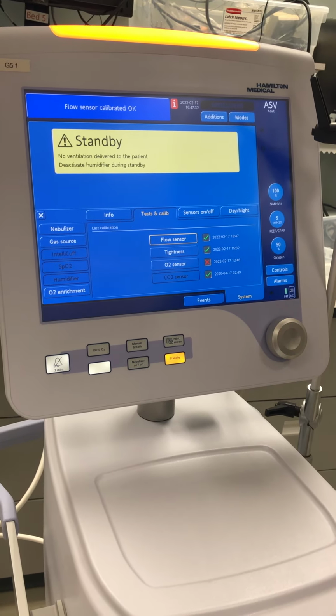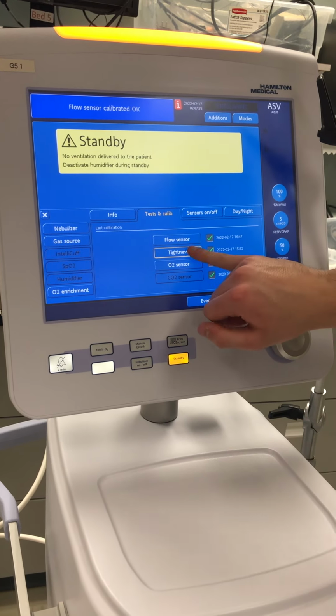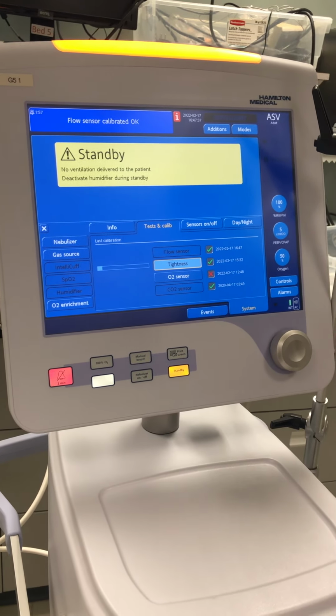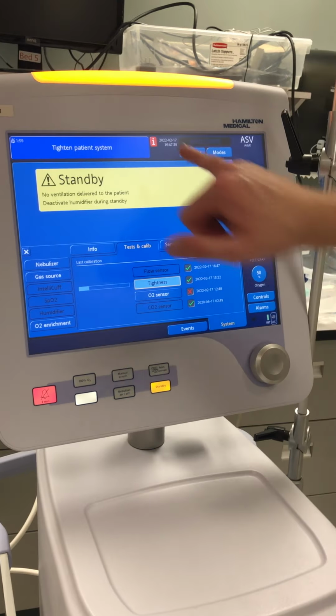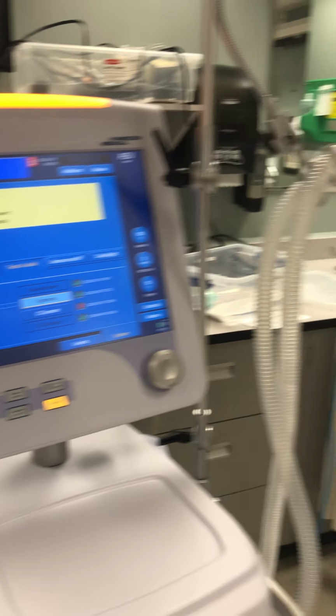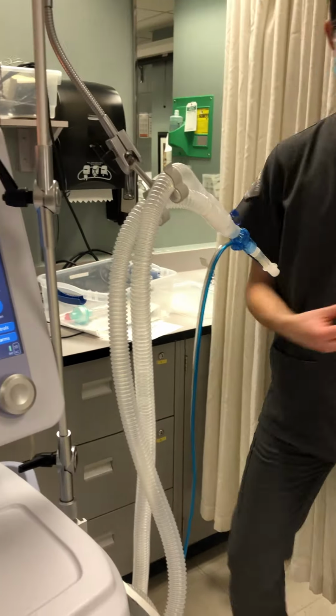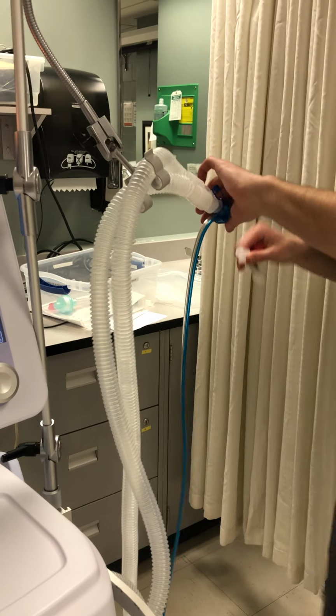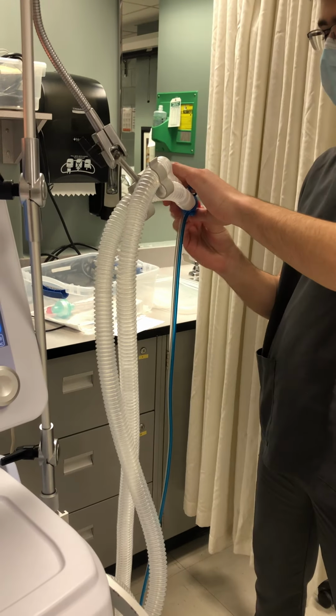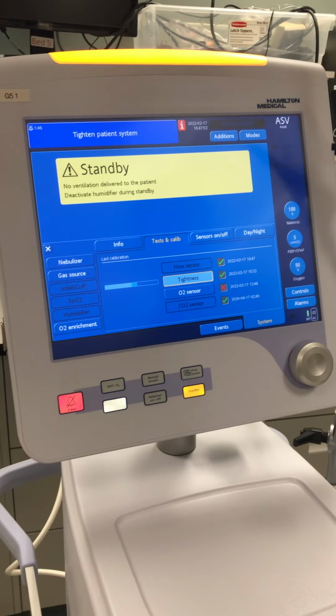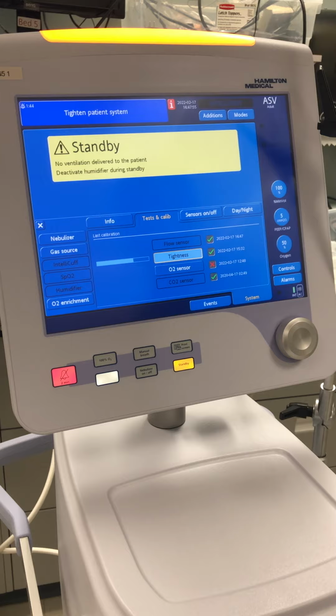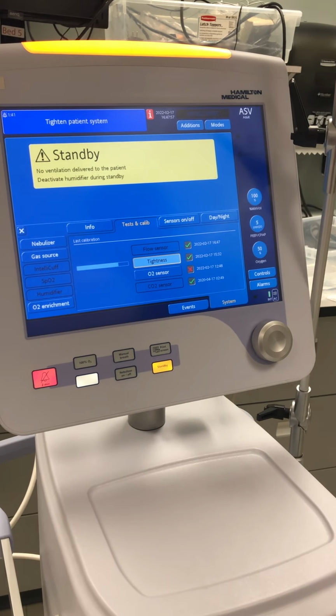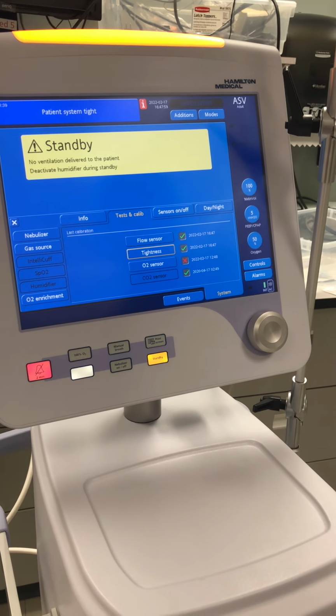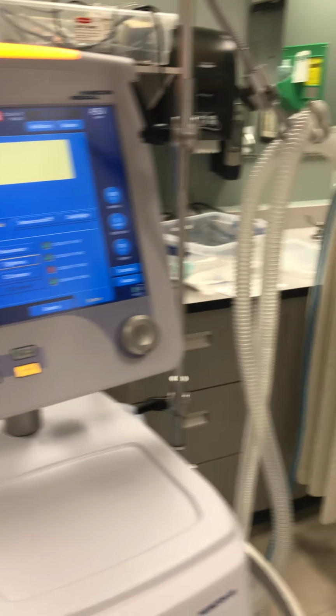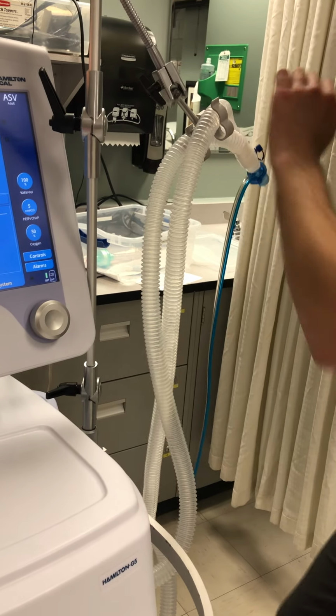And now the other thing you want to do is tightness. You press tightness. With tightness, it will say tighten patient system. What that means, and it's a weird lingo, you take this cap and you block the Y, and that's it. When you do that, you'll notice the progress bar starts going. So tighten patient system just means block the Y. I don't know why it's called tighten. It is what it is. Patient system tight, you can take off the Y now.